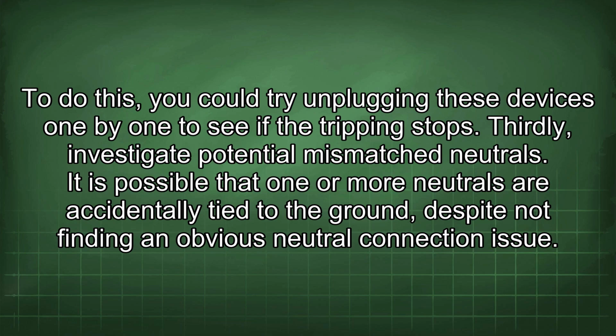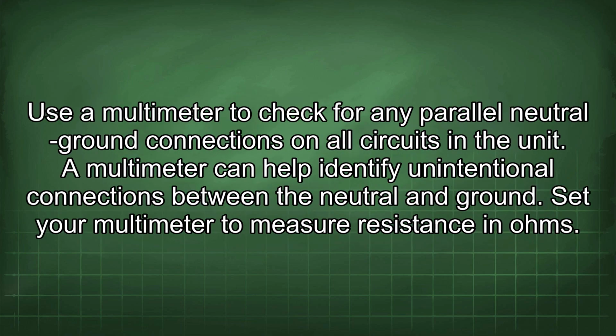Thirdly, investigate potential mismatched neutrals. It is possible that one or more neutrals are accidentally tied to the ground, despite not finding an obvious neutral connection issue. Use a multimeter to check for any parallel neutral ground connections on all circuits in the unit. A multimeter can help identify unintentional connections between the neutral and ground.